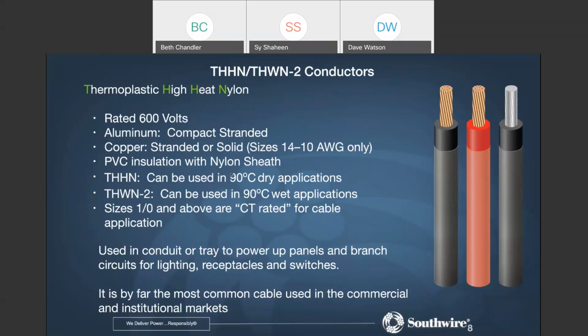So the PVC insulation is the insulation. It's what's primarily there to protect the product and to provide the electrical and environmental protection that's necessary. So this product, the THHN type of product, is going to give you the smallest OD conductor, and it will be the lowest cost conductor for these general building wire type of installations. In conduit, sizes 1/0 and larger are CT rated, as we show, and so therefore they can be pulled as single conductors or plexed conductors within a cable tray.